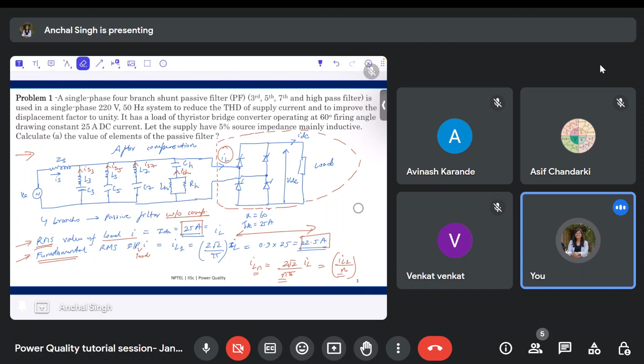Only the active part of the current is supplied by the source. No harmonic component is supplied by the source. But initially, all the harmonic currents were supplied by my source current - all the third harmonic, fifth harmonic, seventh harmonic, and ISH - everything was coming from the source.